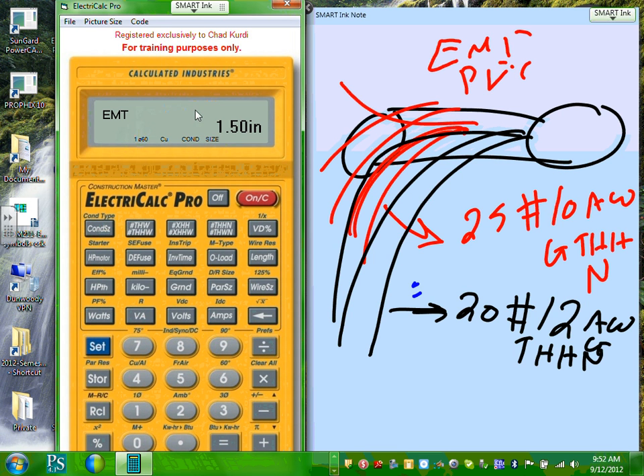Let me do it one more time because this gets tricky. When you have different sizes, here's how you do it, guys. First, you start with the first size. What's the first size? 10. Hit the wire size. You should see AWG 10. Then, how many of them do you have? 25. Here's 25. What insulation? THHN. When you see the THHN, hit the THHN again. You should see the square inches. Now you're done with the first set.